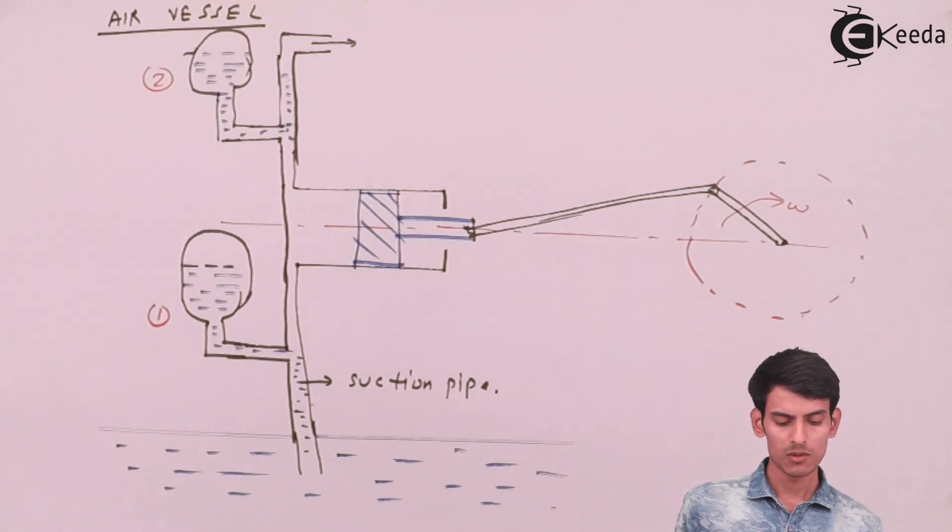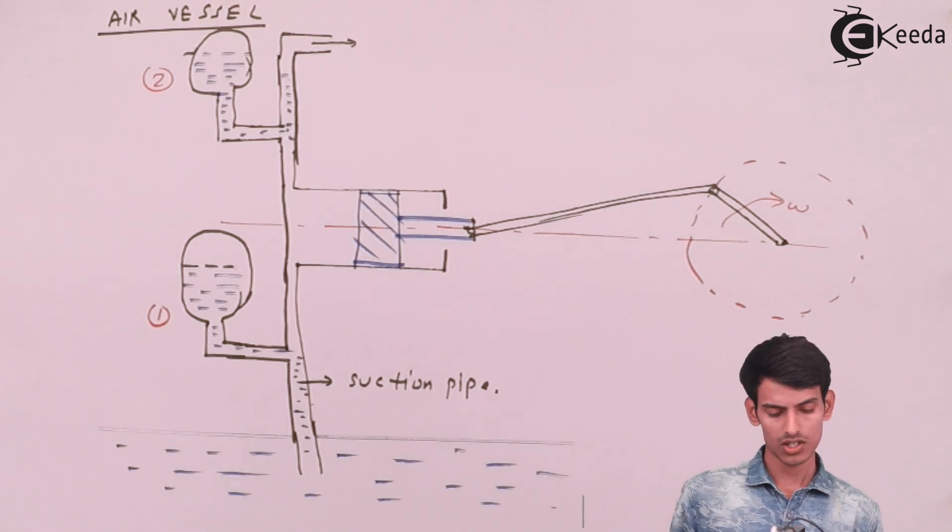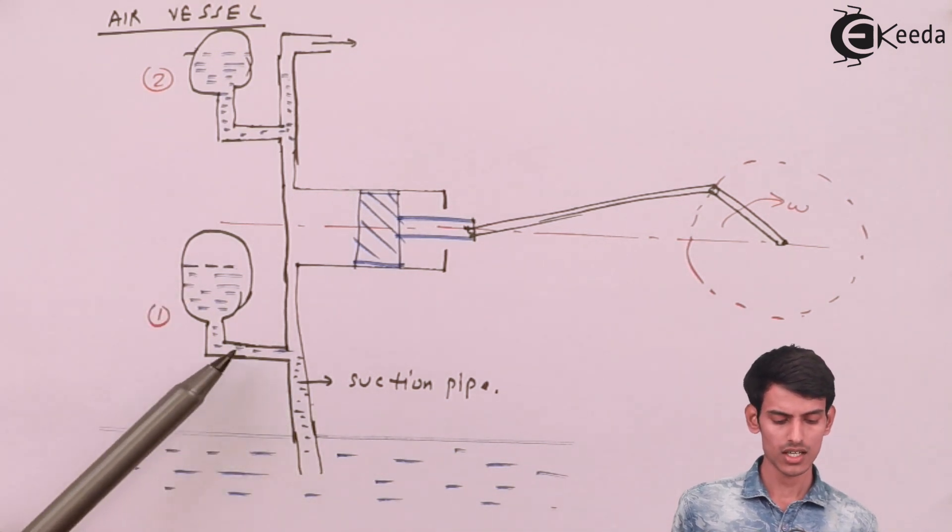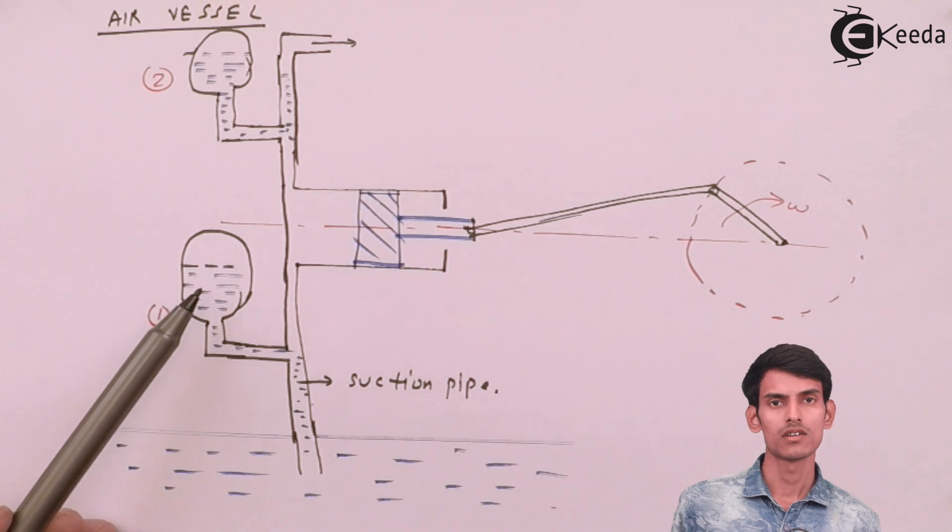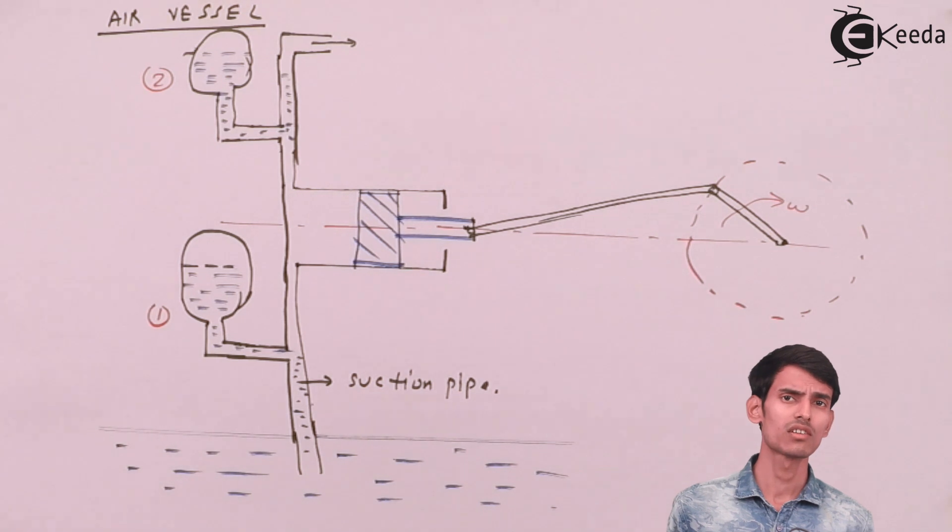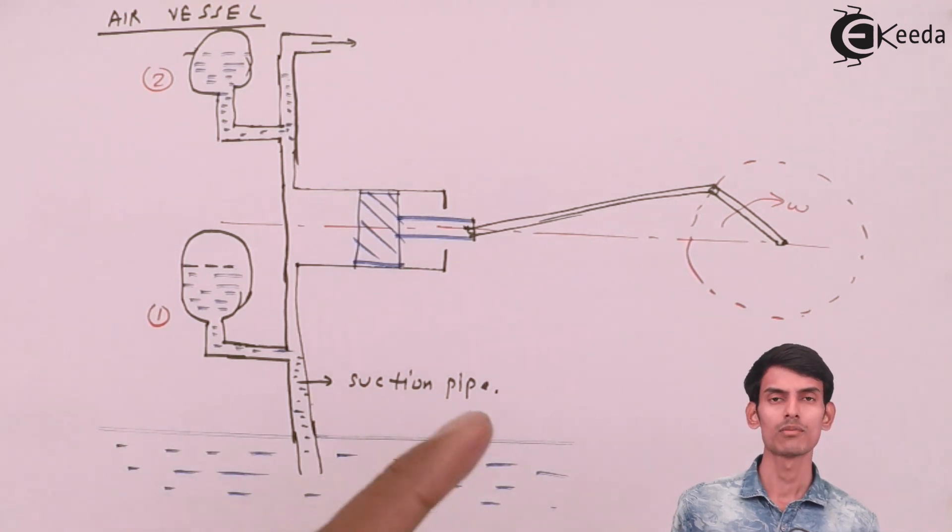So what happens is, suppose it is filled with air, the water is being sucked into the pump from the suction pipe. Now since there is a connection with this container, the water first enters into this air vessel, and then after the air vessel is filled to a certain level, the water starts flowing into the pump.